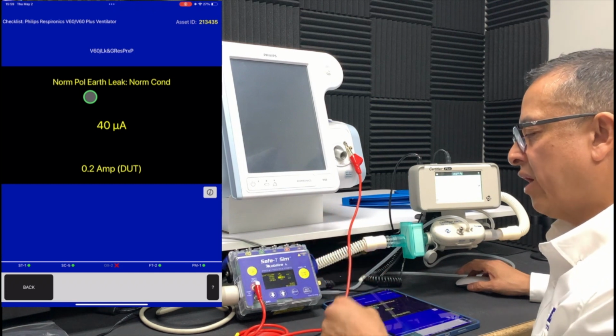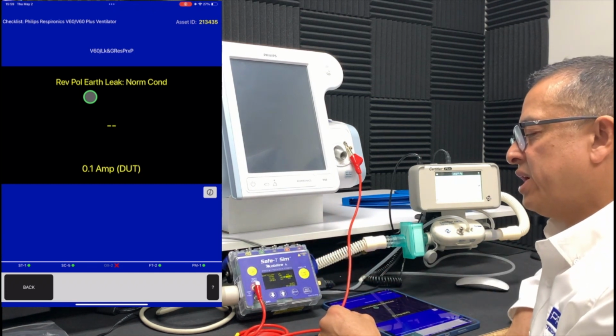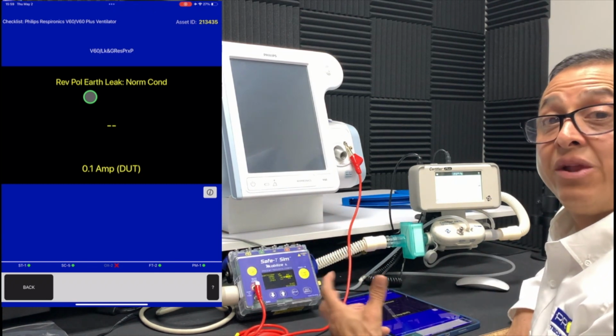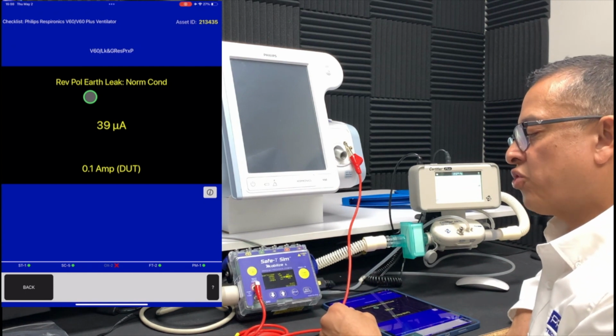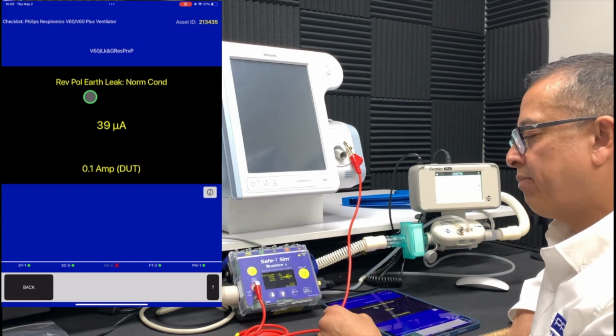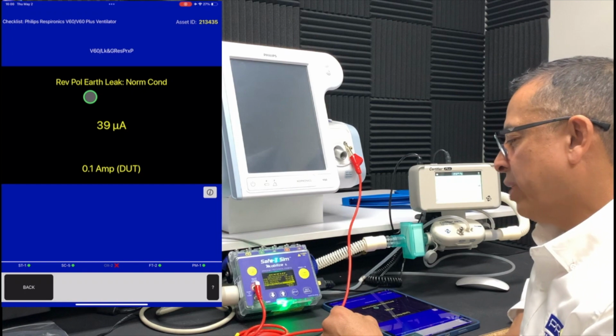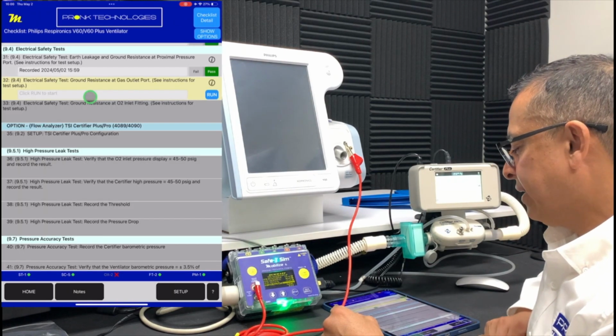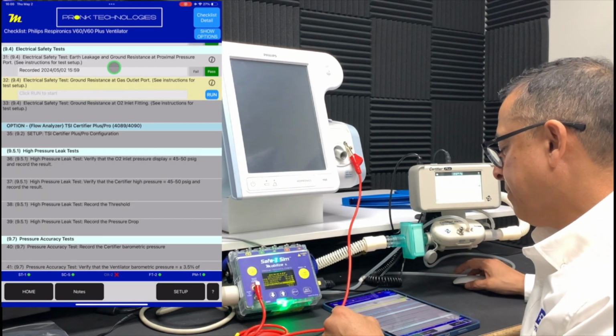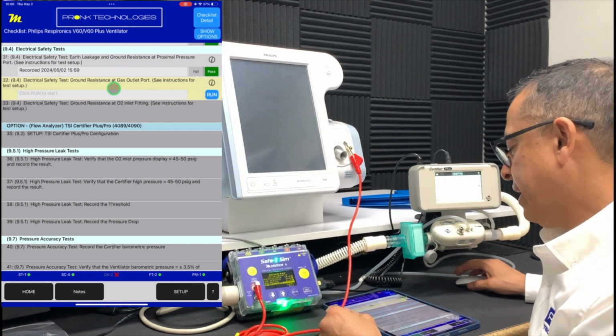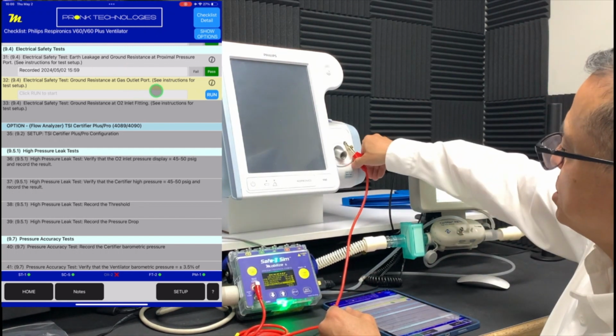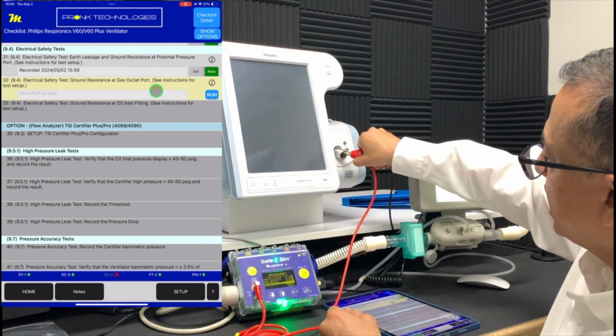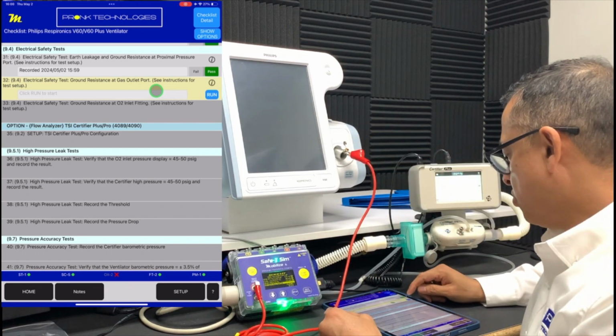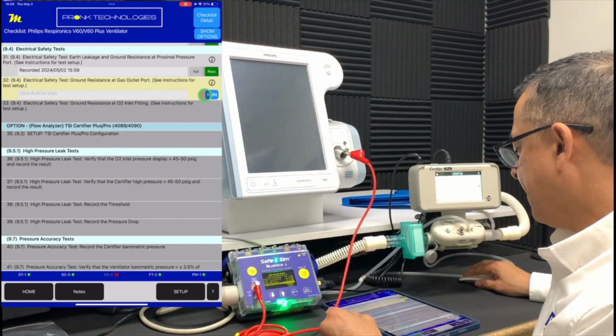This particular ventilator wants us to do the earth leakage test in normal polarity and in reverse polarity with the neutral closed. So we need to make sure we're running in both directions. That's why we're doing it this way. Once that test is complete, it completes that step and we go on to the next step. The next step wants us to do the ground resistance test on the gas port. So we want to collect those results as well. So we connect it to that and run that next test.